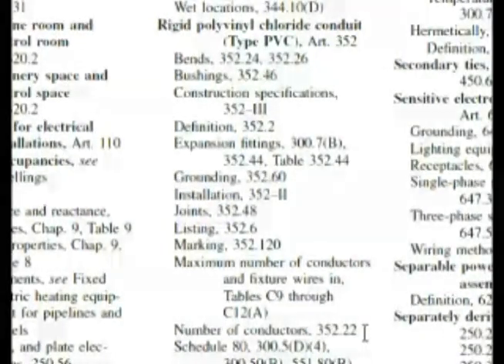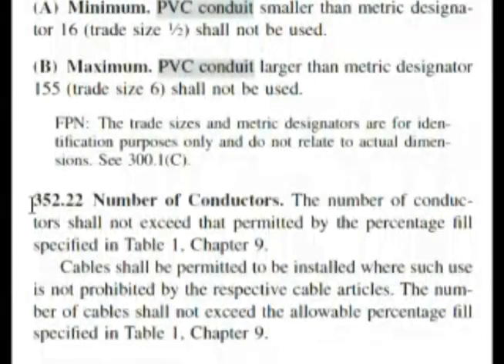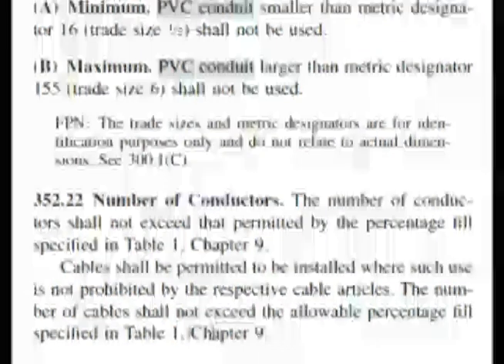Our next thing in the index is number of conductors. The wording of our question was 'number of conductors permitted in PVC conduit' — that's where we're going to look: 352.22. Here we are at 352.22, number of conductors. It says the number of conductors shall not exceed that permitted by the percentage fill specified in Table 1, Chapter 9. And that was one of our answers. It continues: the number of cables shall not exceed the allowable percentage fill specified in Table 1, Chapter 9. This is answer A of our question.